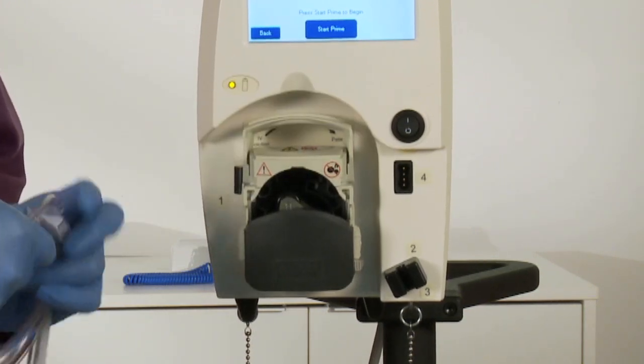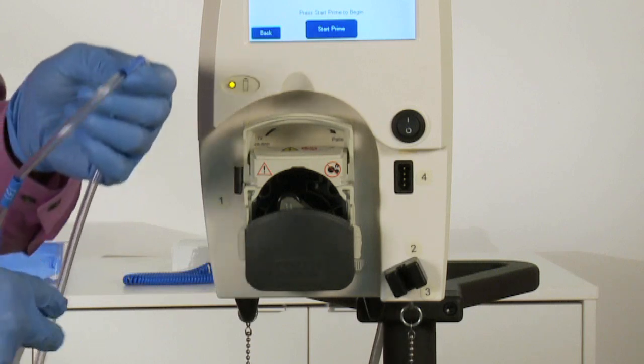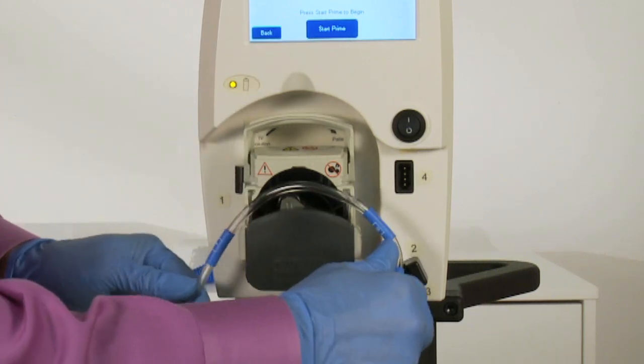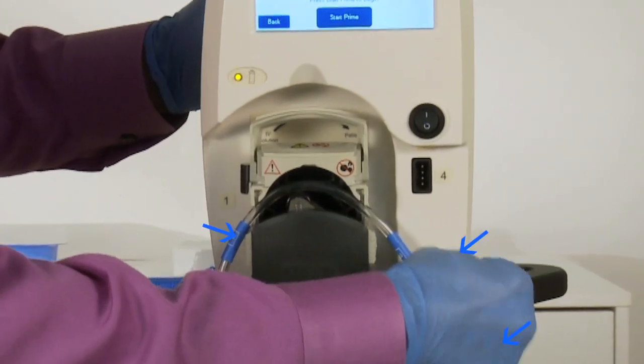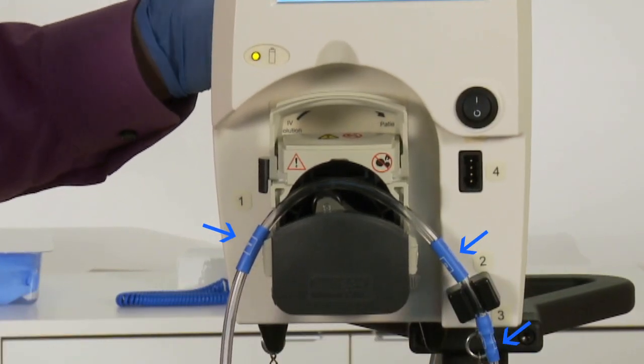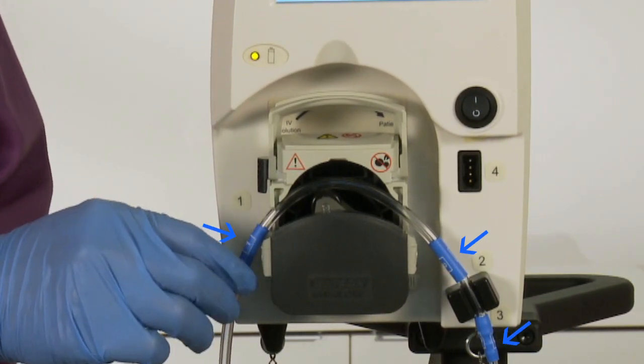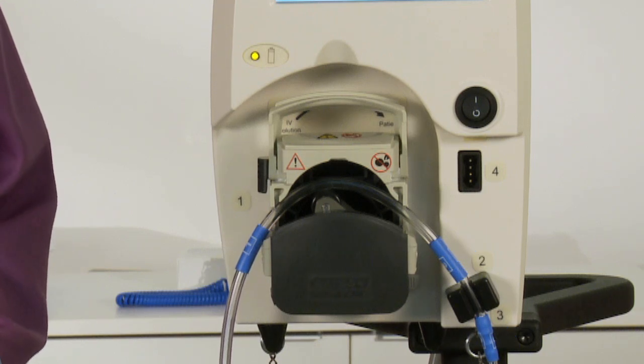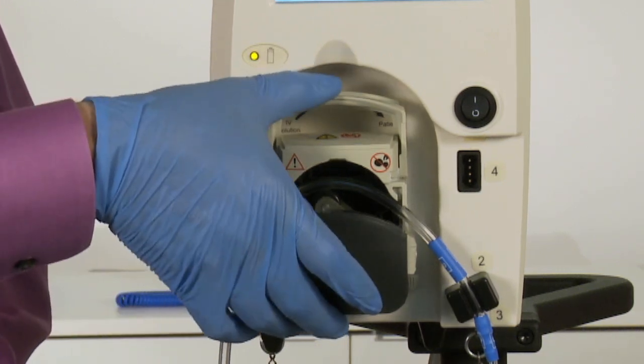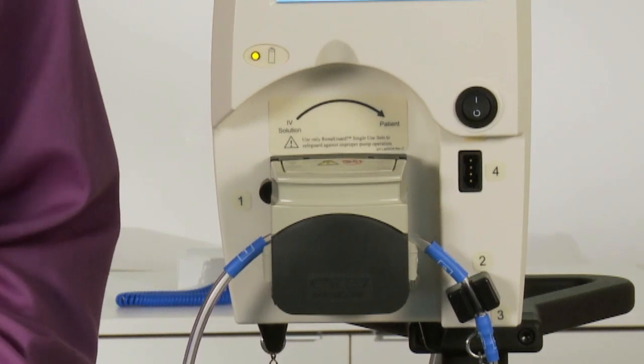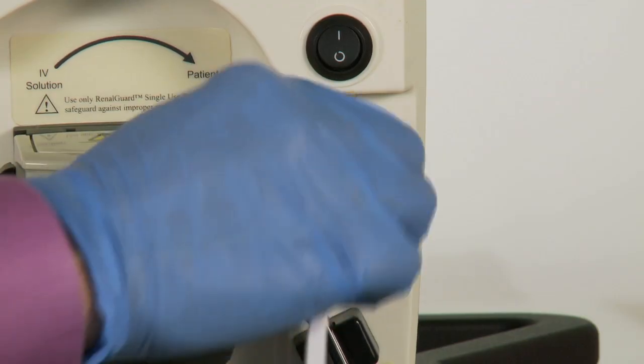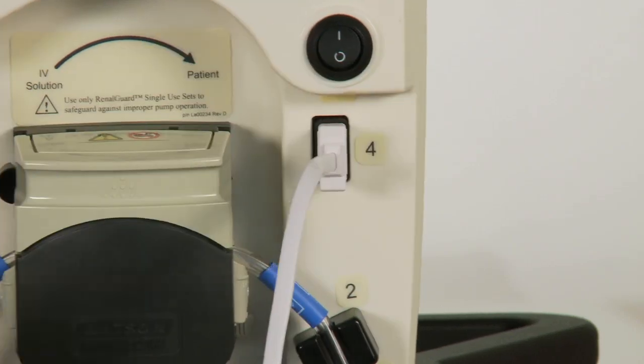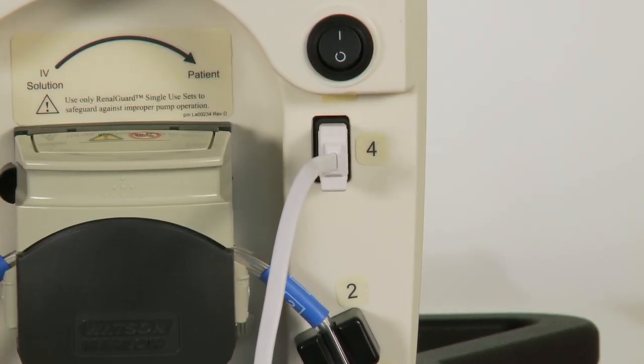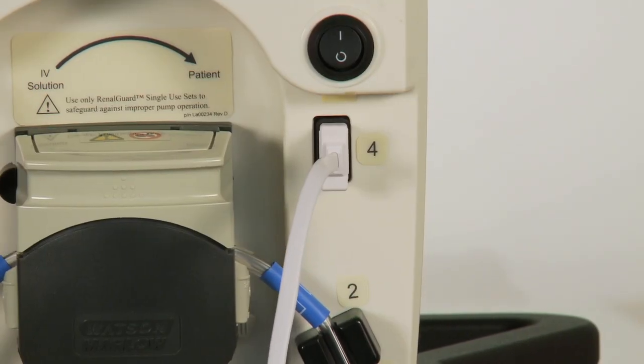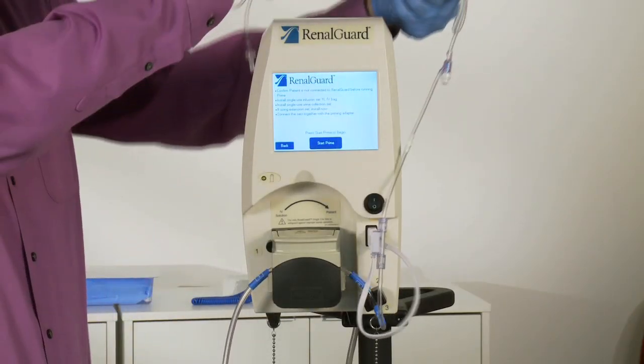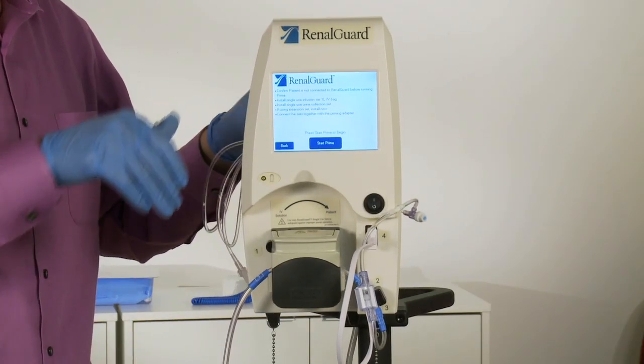Now open up the pump door and thread the infusion set through the pump. You'll see a 1, 2, and 3 on the console. They correspond to a 1, 2, and 3 on the infusion set. Put the 2 and 3 around the air detector and push the tube in there. Make sure the 1 is lined up and close the pump door. Now connect the pressure transducer marked 4 into the transducer receptacle also marked 4. Make sure the connector is fully seated. The connector can be inserted in either direction. The infusion set is now installed. Drape it on the console to keep the end from dragging on the floor.